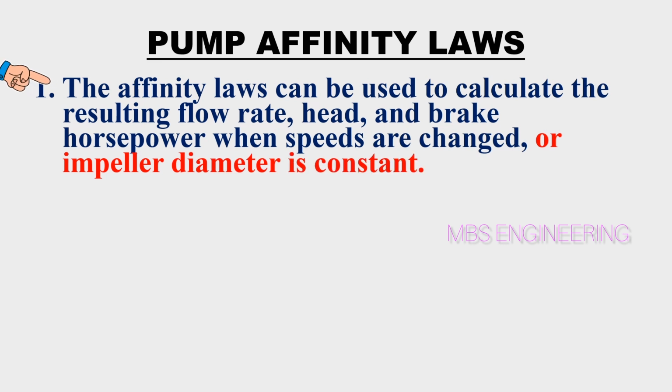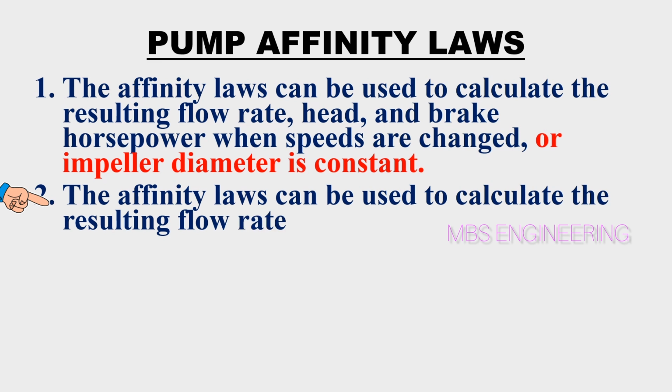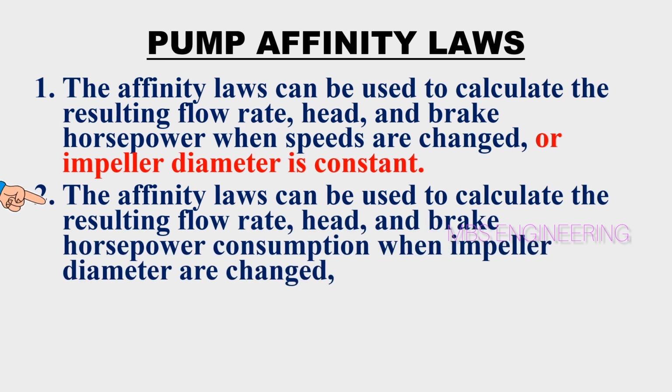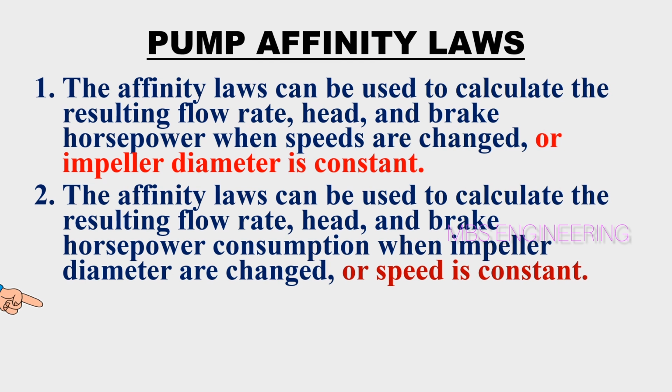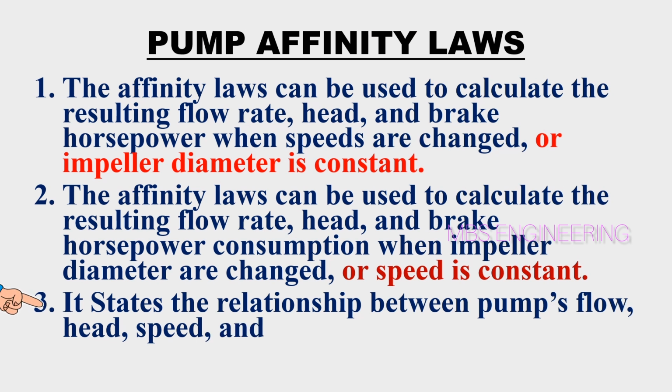The second point is, the affinity laws can be used to calculate the resulting flow rate, head, and brake horsepower when the impeller diameter is changed, or speed is constant. The third point is, it states the relationship between the pump's flow, head, speed, and brake horsepower.